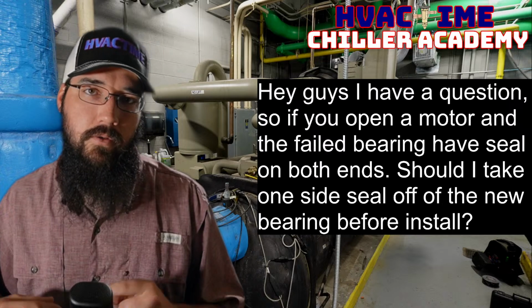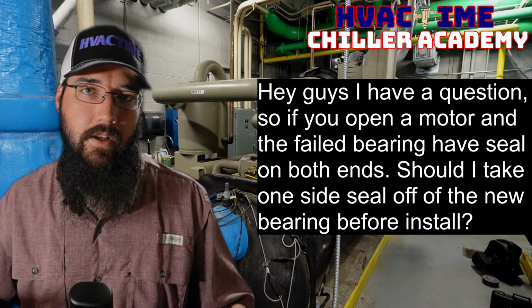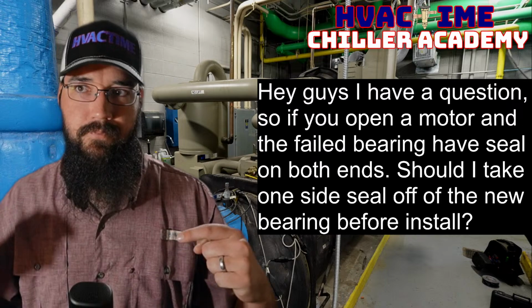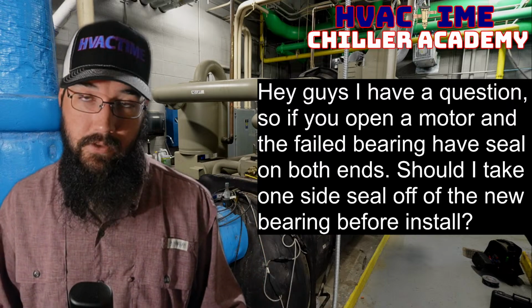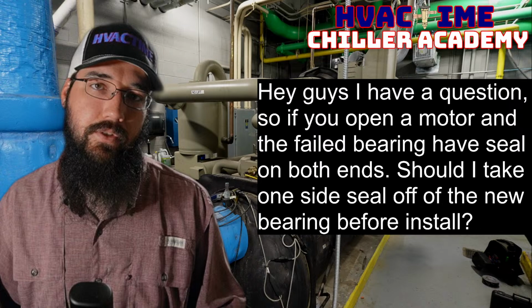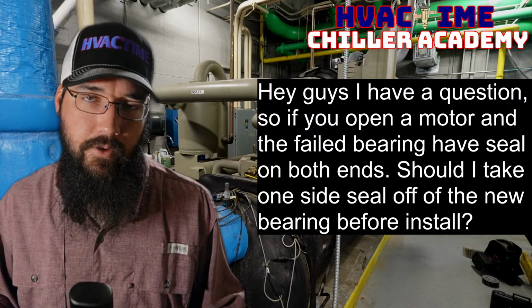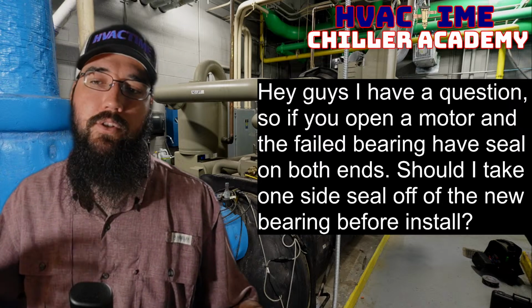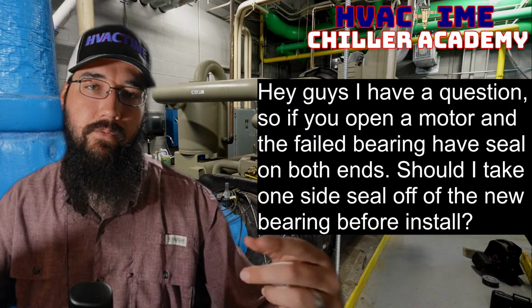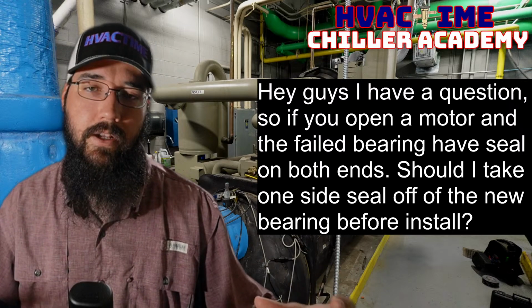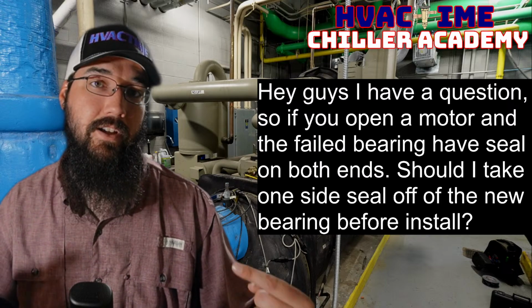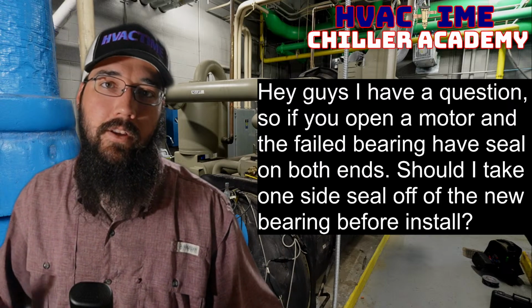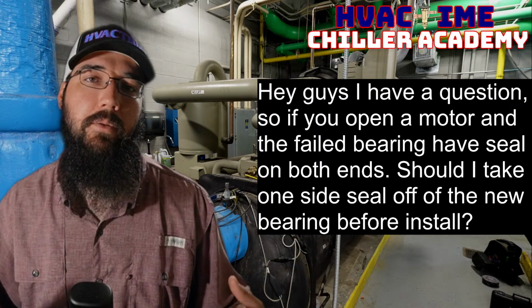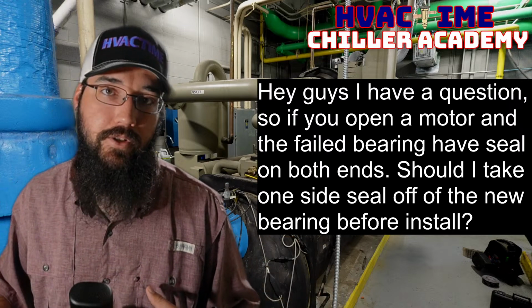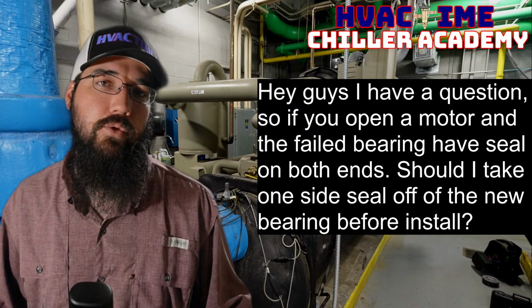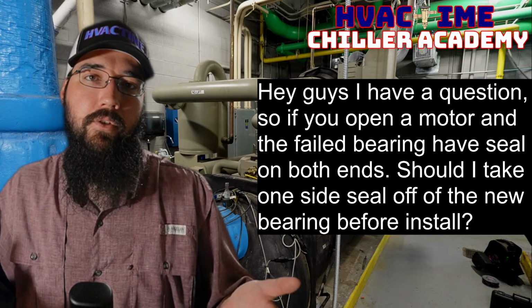Don't install non-shielded bearings in a motor like that. You will just make a complete mess of everything, especially that motor stator, and that will cause a premature failure because all of those are air cooled, which is why they've got the little fan mechanisms, whether internal or external, however they're doing it. All of those are air cooled, and that grease becomes an insulator, just like oil in the refrigerant circuit coating the tubes becomes an insulator to the tube and causes approach issues and heat exchange, right? Well, that grease will do the same thing to our motor, will cause our motor temperature to rise.